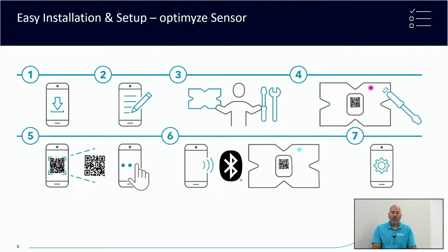Here are some pictorial instructions. This would be sent with each unit. There are descriptions associated with each one. However, step 1 here is just telling you to download the optimyze mobile application. Step 2 is telling you to register for it. Step 3, take the optimyze sensor out, and with each optimyze sensor, there's going to be shipped a screwdriver. On the back of the screwdriver, there's a magnet. That's how you wake up the sensor and how you put it in pair mode.